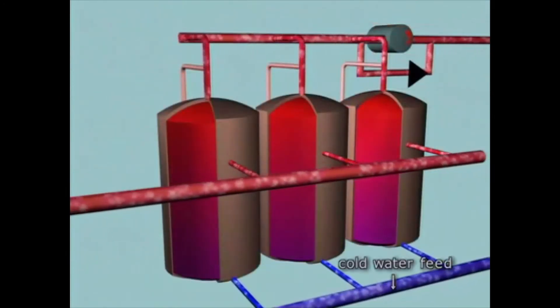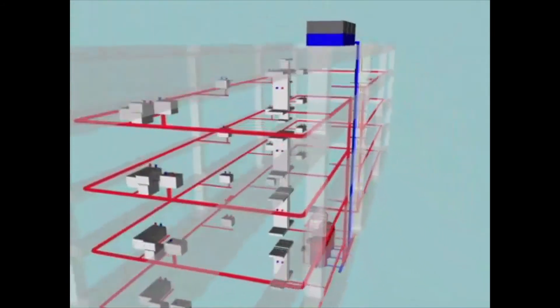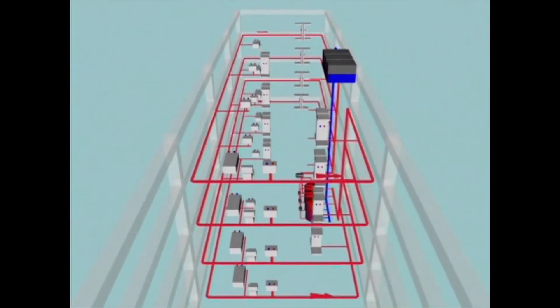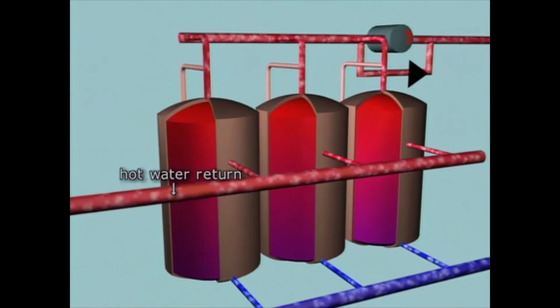The cold water feed pipe enters at the base of the calorifier. The heated water is drawn off from the top of the calorifier and pumped into a distribution circuit referred to as a ring main. When it has completed its journey around the ring main, the water is returned to the calorifier for reheating.